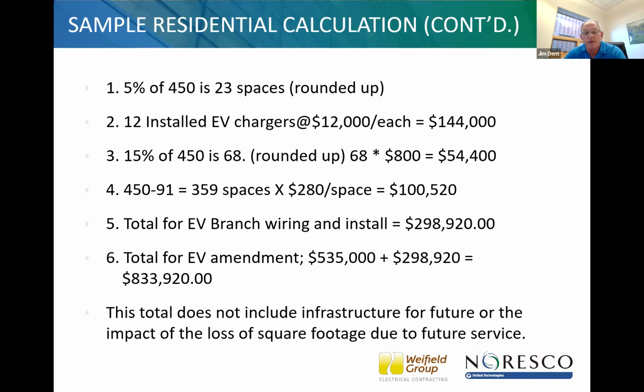15% of 450 is 68, rounded up again. 68 times $800, which is the cost to run a 100-foot, 3/4-inch conduit with a 40-amp circuit in it, is $54,000. And then the remainder of the spaces, 359, would have to have an empty conduit, which is $280 for a 100-foot average, for around $100,000. So the total for the EV branch wiring and install is $298,000.